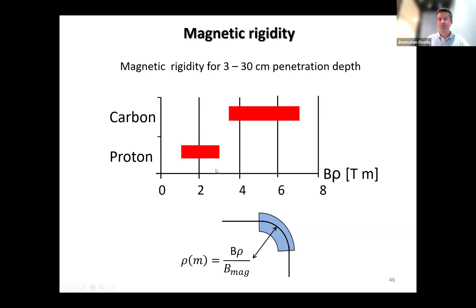So that means that if you want a machine that is able to bend and control the beam and keep it inside the ring, then if you want a smaller bending radius, you need a quite high magnetic field. And for this property, the B rho, the magnetic rigidity, in order to get the energy at which the particle beam, either proton or carbon, is able to penetrate to at least 30 centimeters depth, you get basically these constant numbers: around 3 for the magnetic rigidity for protons and around 6 for carbon ions. It might not mean much, but believe me, it's the real reason why these machines are so big. This is a photo of the carbon ion gantry at Heidelberg, and this part here is only the last bending dipole.